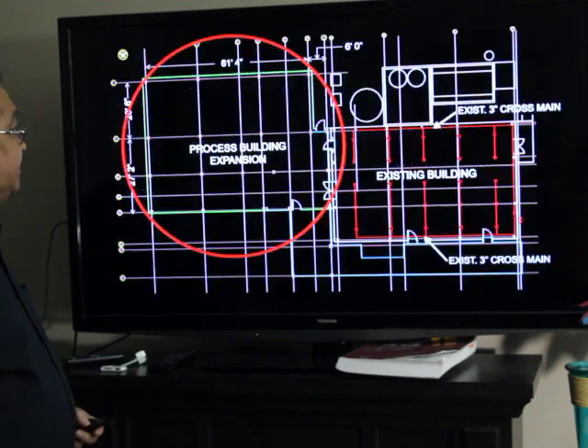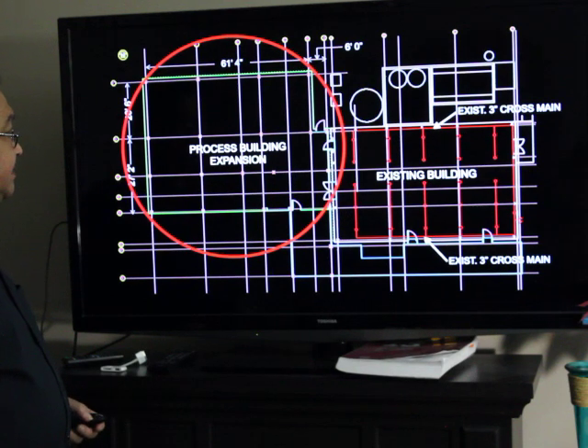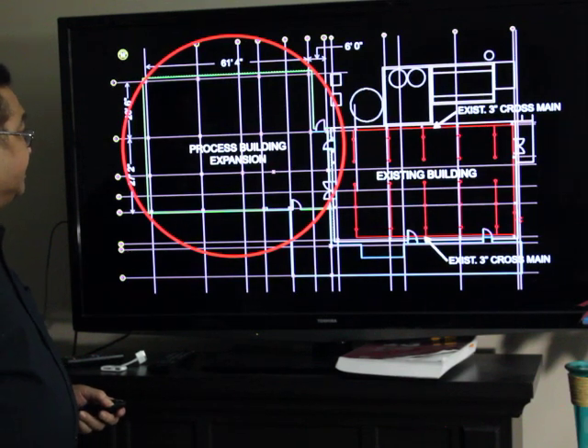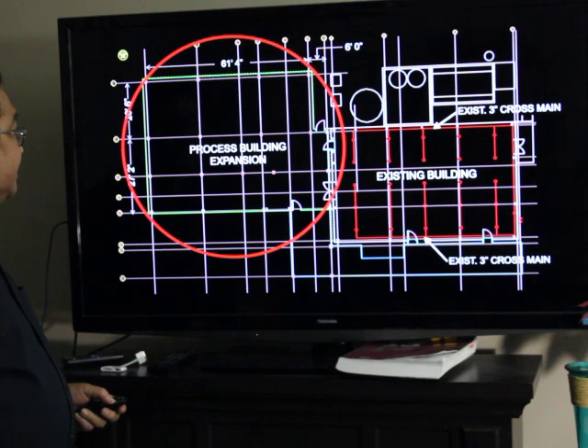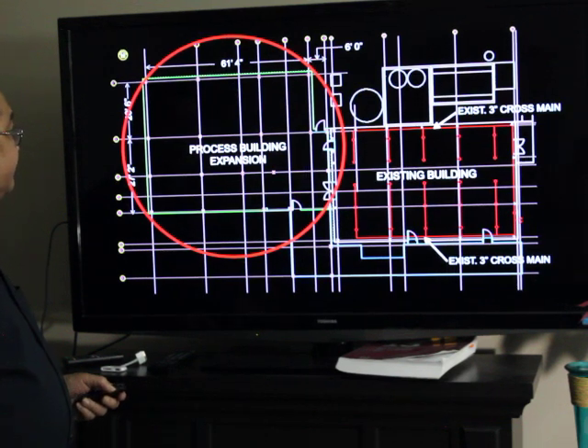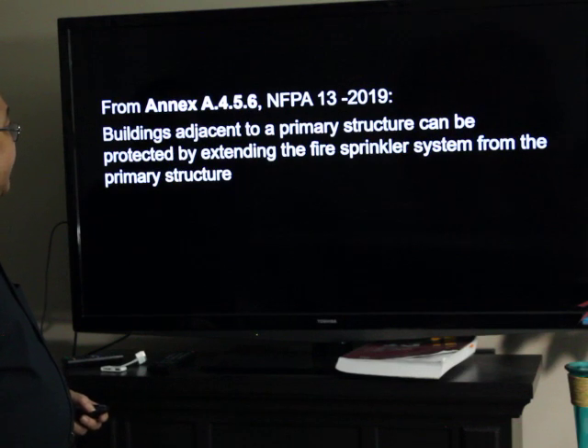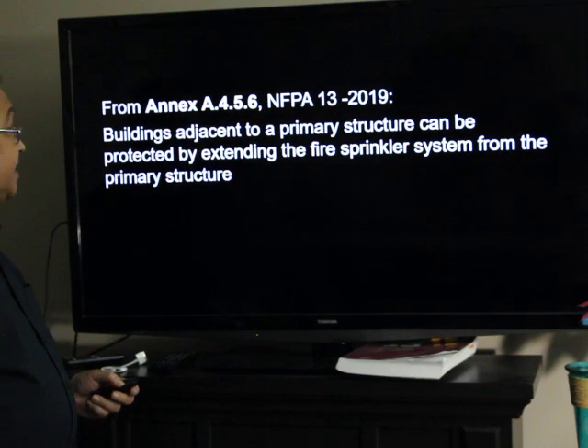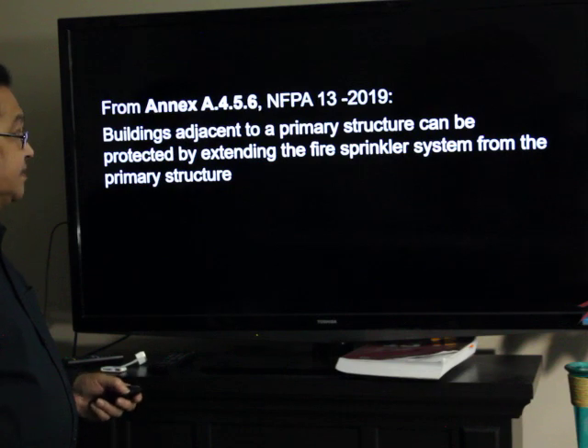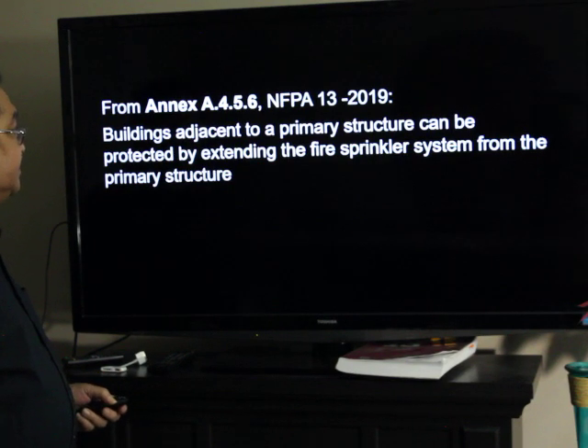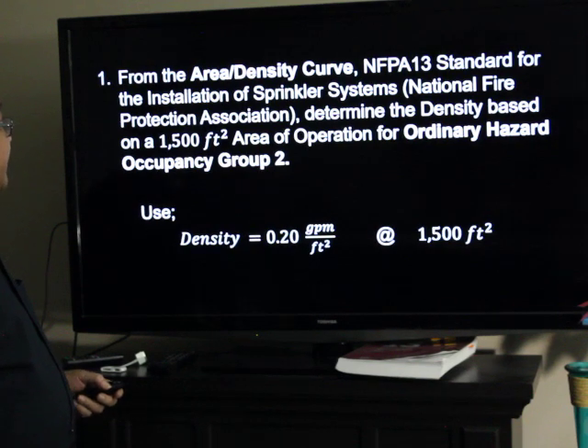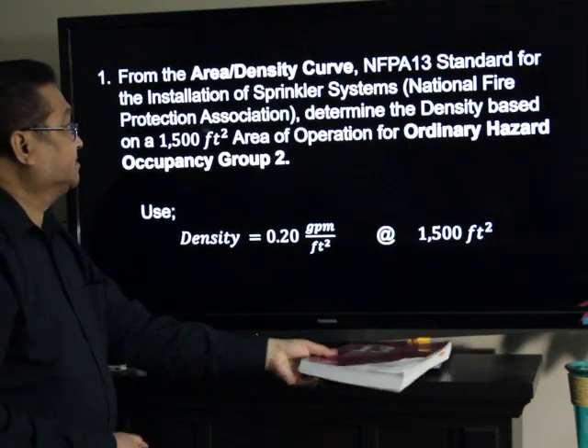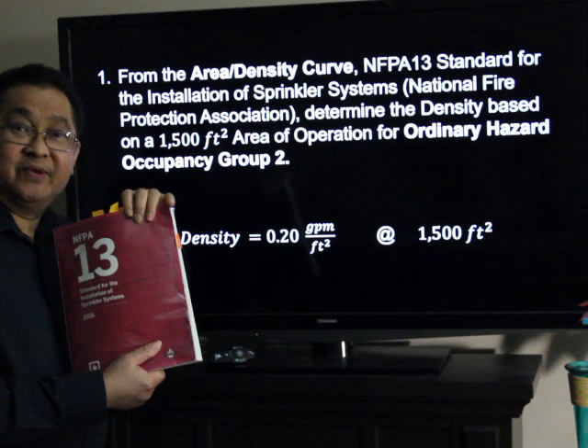In this drawing, you will see on the right the existing building with its existing fire sprinkler system. And on the left side, encircled here with red, is the process building expansion. From Annex A.4.5.6, NFPA 13, buildings adjacent to a primary structure can be protected by extending the fire sprinkler system from the primary structure. From the area density curve, NFPA 13, standard for the installation of fire sprinkler systems — this is a copy of the standard.